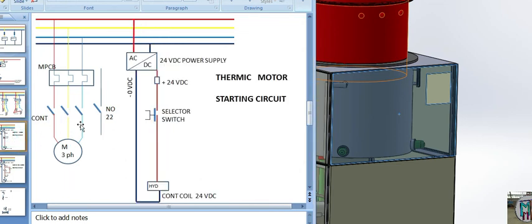And if you are fixing one selector switch, you can connect directly, because you have fixed the MPCB here, so a 24 volt DC power supply. If you want to fix a 24 volt DC contactor, fix one power supply there, and after the fuse fix a switch, fix a fuse, and connect the minus voltage directly in the relay. And when the selector switch is on, current will pass and the relay coil will be on. So at that time you will get supply in both heaters at the same time.